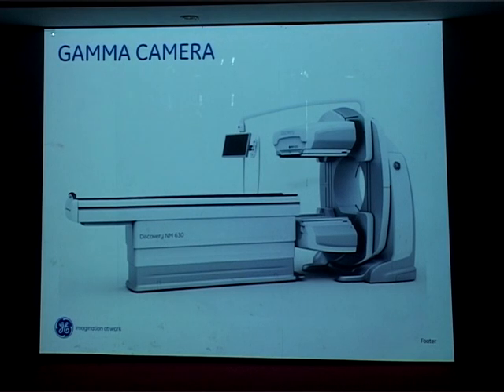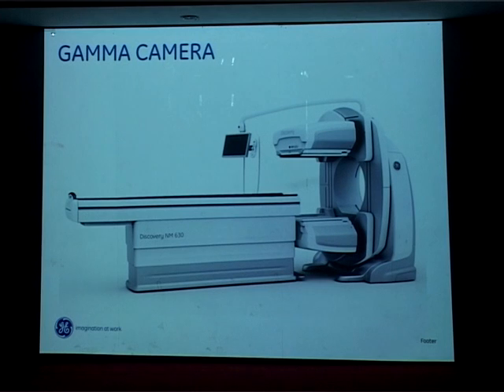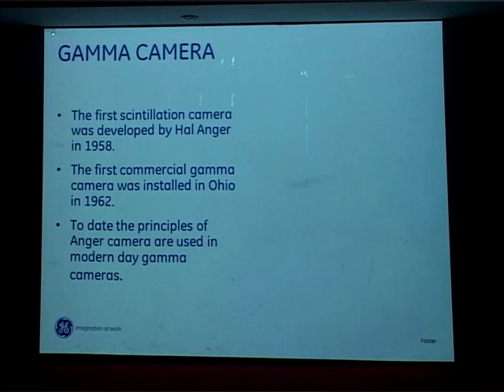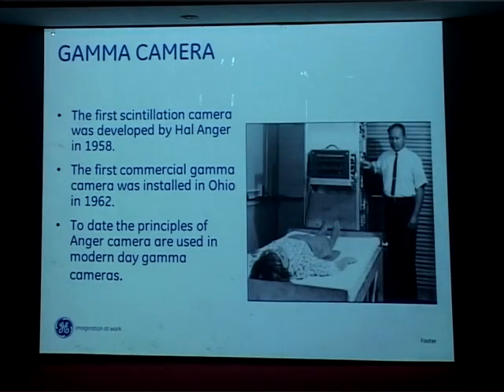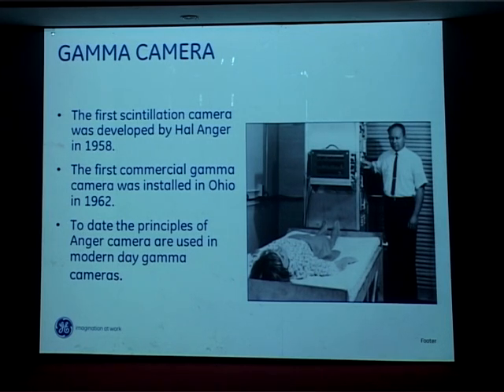I will first start with the gamma camera, which is where nuclear medicine and molecular imaging started from — just as X-rays are the base for radiology, for us it is always the gamma camera. The first scintillation gamma camera was developed by Anger in 1958, and the first commercial gamma camera was installed in Ohio in 1962. Today the principles of the Anger camera are still used in modern-day gamma cameras.